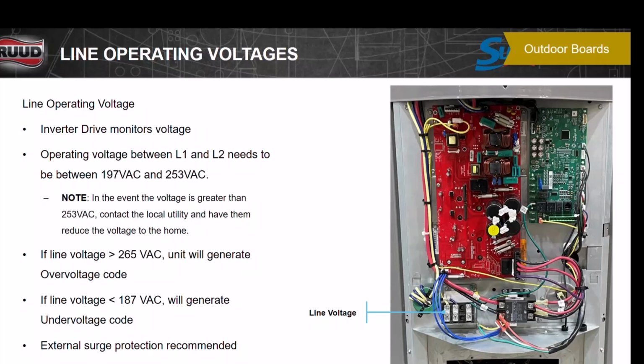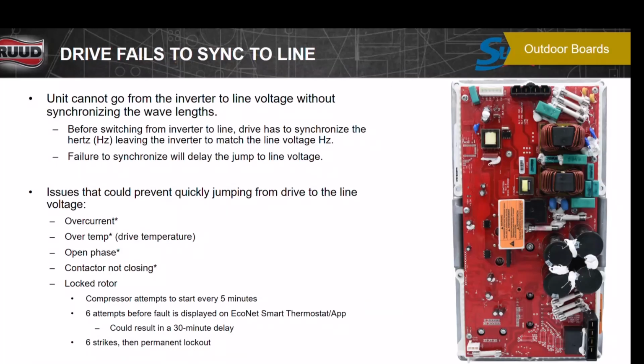The unit cannot go from inverter to line voltage without synchronizing the wavelengths. 60 hertz, right? As that unit's running, we're flowing from 40, 45, 50 hertz. It's got to synchronize the wavelengths before it changes. So that's why it gets up to that 65% and 70%. The waveforms are close, bam, it switches. So it cannot do it. Anytime that we try to speed that up manually, it's going to be a bad outcome.